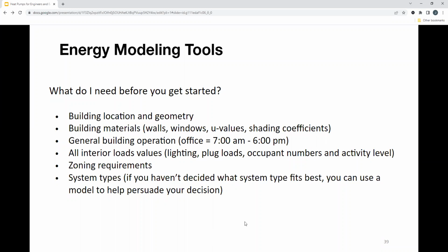And then general building operation. Is this a multifamily building that will be running 24/7, where people need cooling and heating all the time? Or is it an office building with hours of 7 a.m. to 6 p.m., where after that you can focus on some kind of setback schedule or what have you? Then all interior load values: lighting, plug loads, occupancy numbers, and activity level. Are we going to have 20 people in an office space, sitting at a desk, or are we sizing for a gym with a larger load? We've got to know all that information.